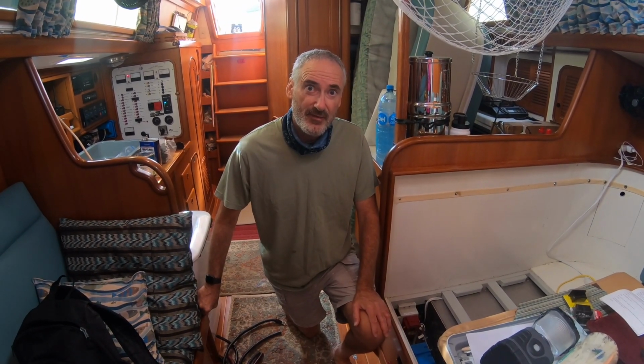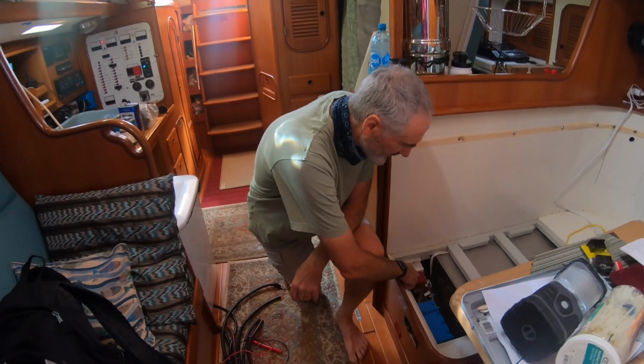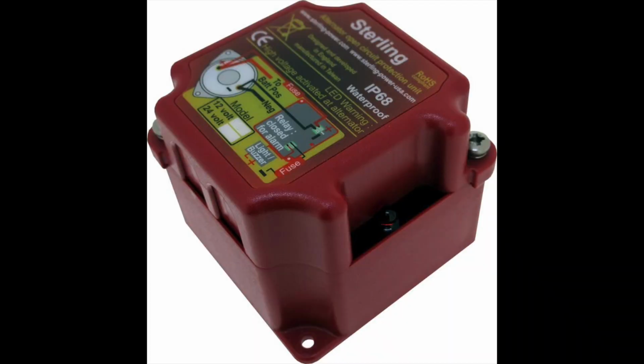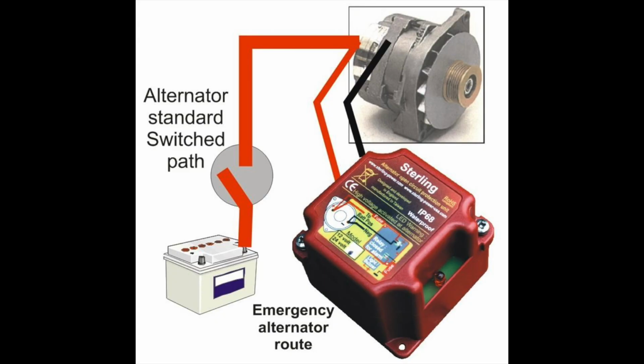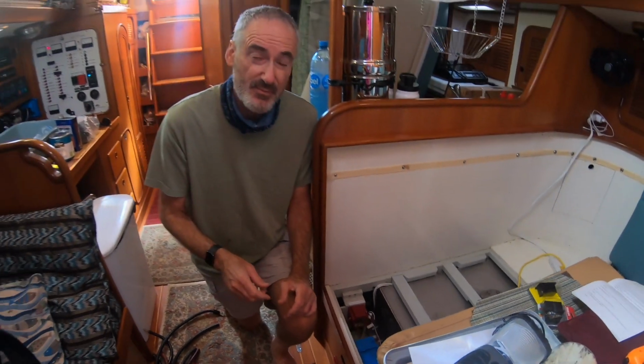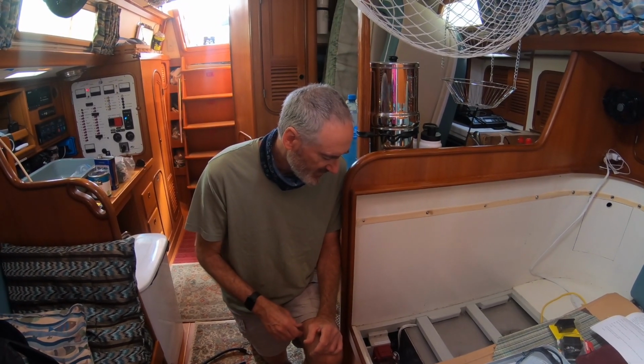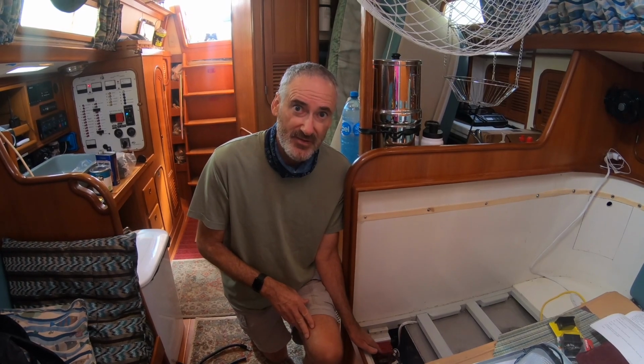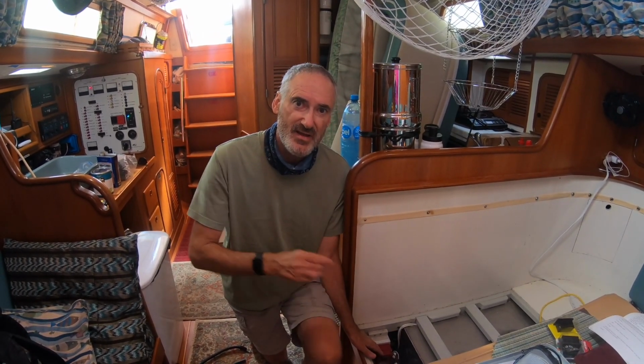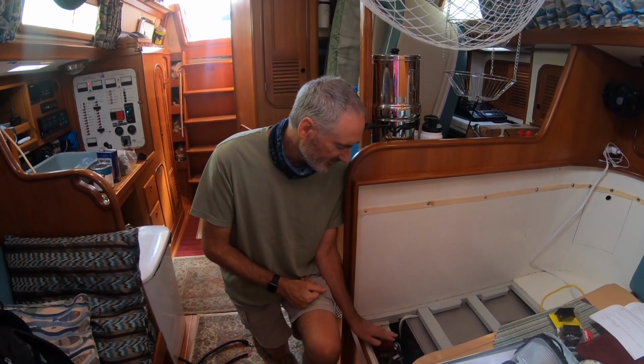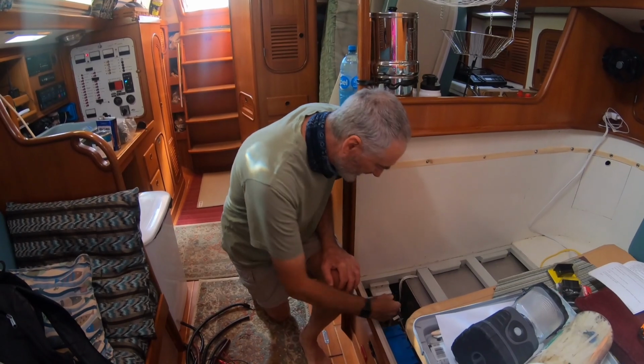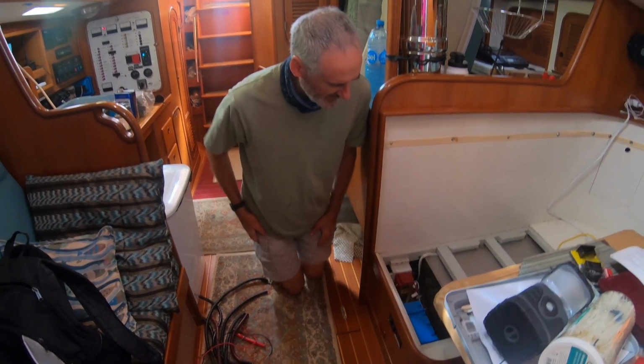One of the things we installed for the lithium battery upgrade was this alternator protection device. What this does is protect the alternator if the lithium battery management system shuts down the batteries due to any excursion, like over temperature, under temperature, overcharge, undercharge, overcurrent, or undercurrent. Without this, it could potentially ruin the alternator if it was doing a full charge and the battery shut down automatically. So this protects against that, and it's all wired up nice and neat. The alternator is right down here, so it's real close, and it's good.